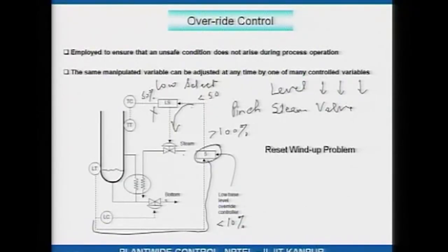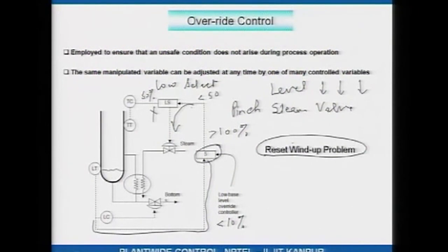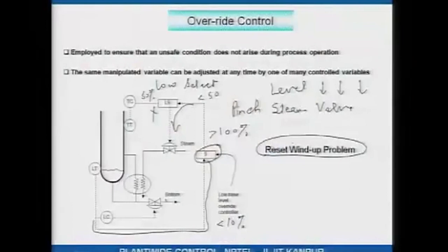This need not necessarily be a proportional multiplier only; it could be a PI controller. If it is a PI controller, note that ordinarily the PI controller will keep integrating and that can cause the output to saturate way beyond 100 percent — this is known as the reset wind-up problem. One has to be aware that override controllers, by their very nature, involve exceptional circumstances that do not normally occur, so the controller if it is a PI controller would actually be saturated due to reset wind-up, and things have to be done to circumvent that problem.